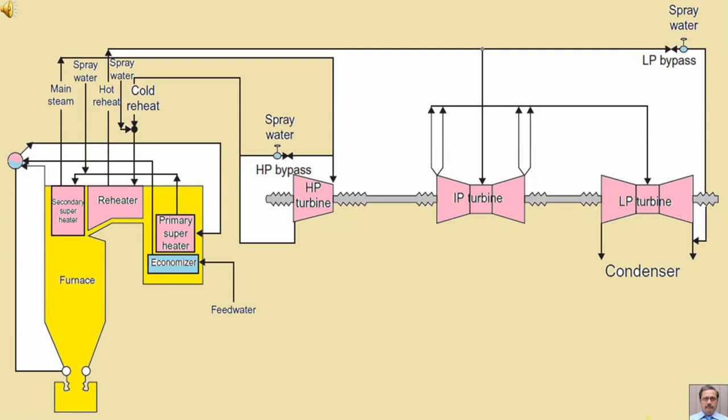In this diagram, we can see the HP bypass system. The HP bypass system is connected between main steam and cold reheat steam. It means it is bypassing the high pressure turbine. That is why it is called HP bypass.